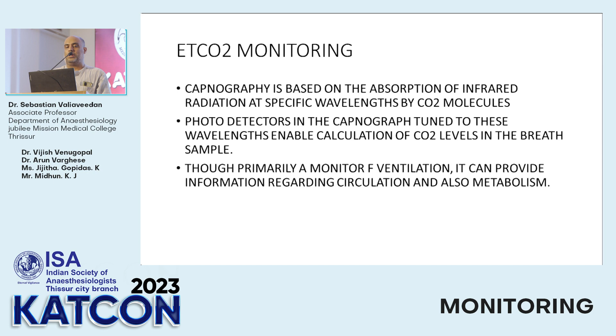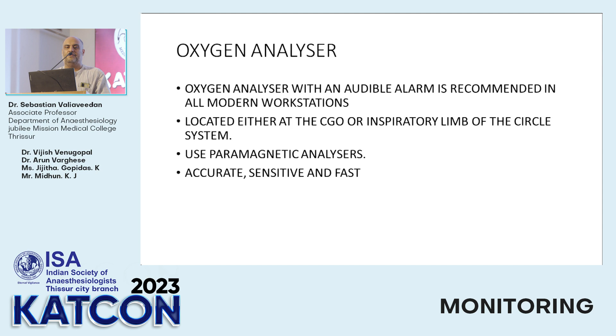And the oxygen analyzer, as we said, is the most important monitor with regard to patient safety. And an oxygen analyzer with an audible alarm is recommended in all modern workstations. It is located either at the common gas outlet or the inspiratory limb of the circle system. And as opposed to the EtCO2 and pulse oximeter, they use paramagnetic analyzers. It's a different kind of analyzer, the principle involved is different. And they are designed to be accurate, sensitive, and fast.